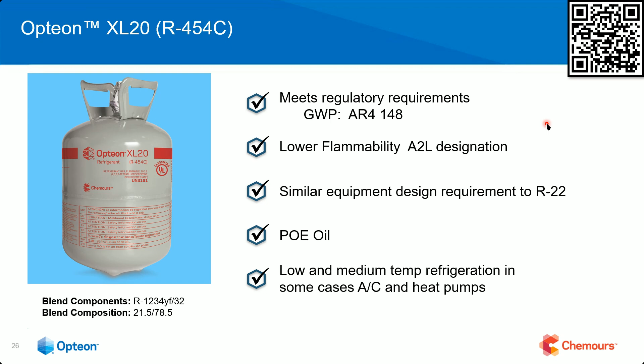So this is going to be for systems over 200 pounds, first and foremost. The performance considerations: capacity delta due to the 150 GWP requirement, and higher efficiency than 404A. Let's just look at that. Here again is our relative capacity. We know relative is going to stand for our baseline, our comparison. We're going to compare 404A again with 449A and 454C.